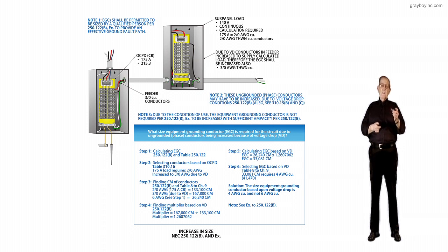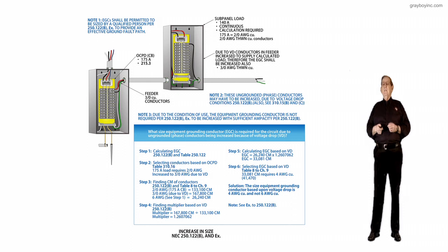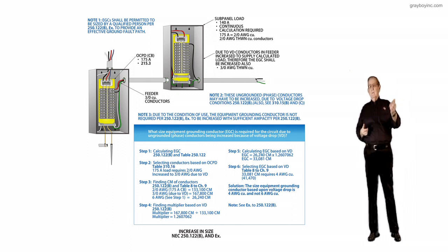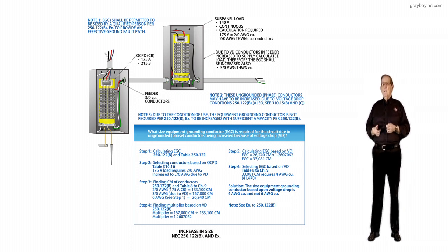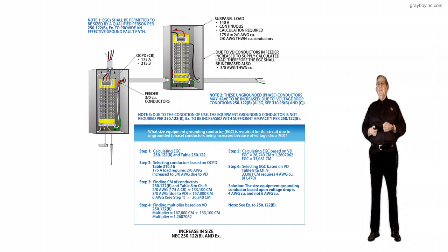Now you've got an effective ground fault path. You'd say, well, no, it has to be 2/0 because we have a lot of neutral load. Then the 2/0 is more than adequate to take care of the number 2. So 220.61 rule there again. See that we've kind of repetitiously told you that because of the revisions in the code.